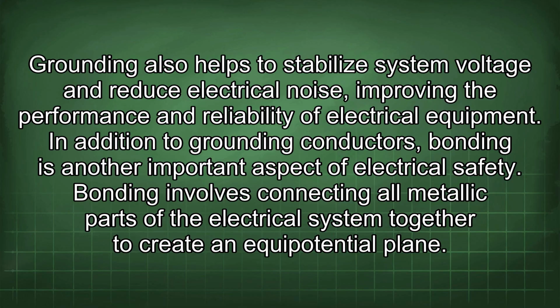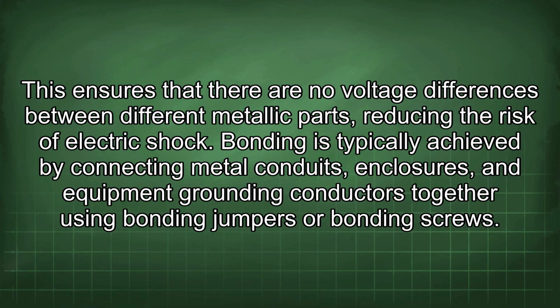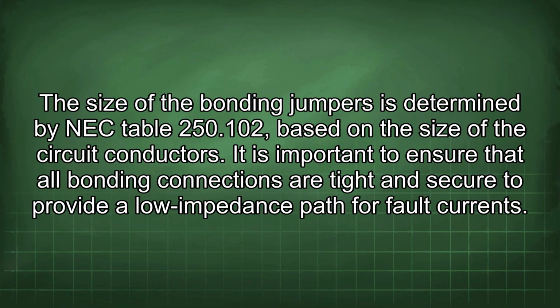In addition to grounding conductors, bonding is another important aspect of electrical safety. Bonding involves connecting all metallic parts of the electrical system together to create an equipotential plane. This ensures that there are no voltage differences between different metallic parts, reducing the risk of electric shock. Bonding is typically achieved by connecting metal conduits, enclosures, and equipment grounding conductors together using bonding jumpers or bonding screws. The size of the bonding jumpers is determined by NEC Table 250.102, based on the size of the circuit conductors.